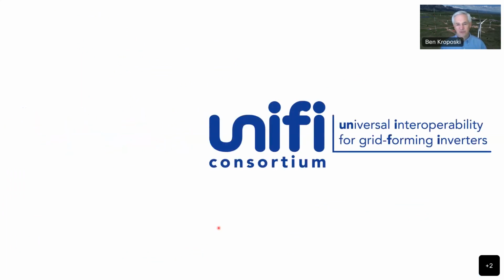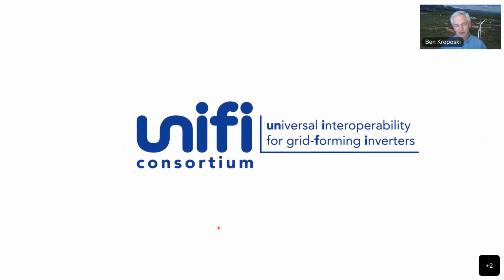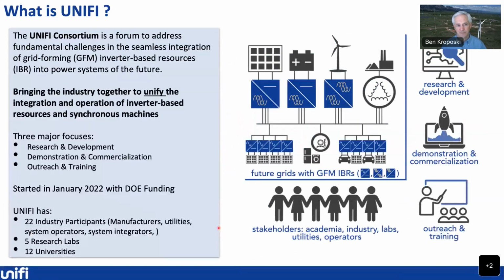So in the US, we've been focused on developing a new consortium called the UNIFI Consortium, which stands for Universal Interoperability for Grid Forming Inverters. This consortium is a forum to address the fundamental challenges of seamlessly integrating grid forming technologies of inverter-based resources, and unifying them with the synchronous generators that exist today. And the key is you have to unify this, because you will have all sorts of different power systems operating with different levels of inverter-based resources and synchronous machines.